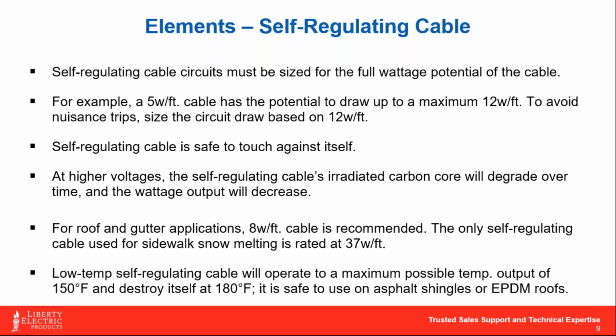Okay. To go down a few of these bullets, though, the big attraction of this cable is that it can touch against itself without fear of burning through. So when you have two warm surfaces like this cable that touch against each other, it wants to back itself down. And the other big appealing part of self-regulating cable is that they actually get categorized between low temp, medium temp, and there really isn't much of a high temp self-regulating cable at this point, mainly because it's a very, very niche industrial type of application.